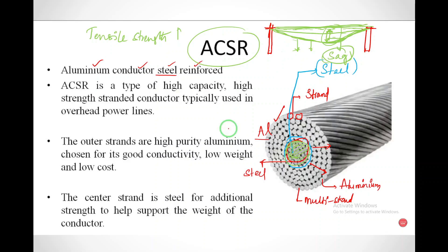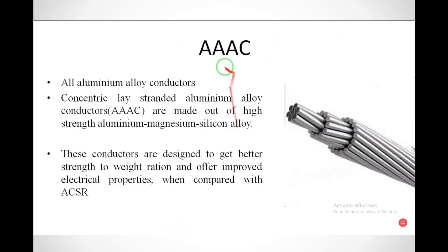ACSR is used for transmission lines. The outer strands are high-purity aluminum chosen for good conductivity, low weight, and low cost. The center strand is steel for additional strength to help support the weight of the conductor.